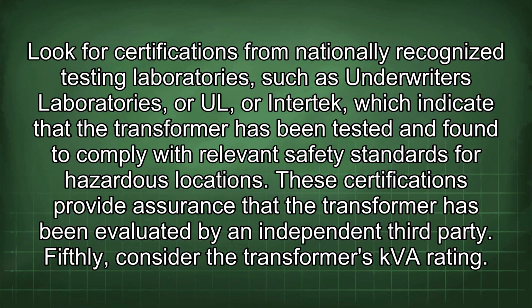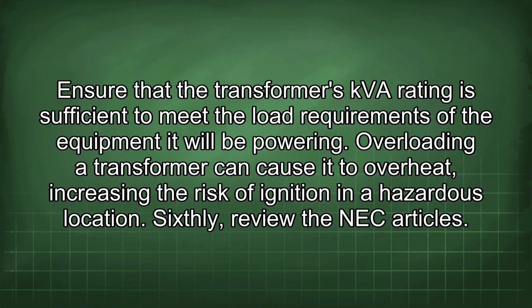Fifthly, consider the transformer's kVA rating. Ensure that the transformer's kVA rating is sufficient to meet the load requirements of the equipment it will be powering. Overloading a transformer can cause it to overheat, increasing the risk of ignition in a hazardous location.